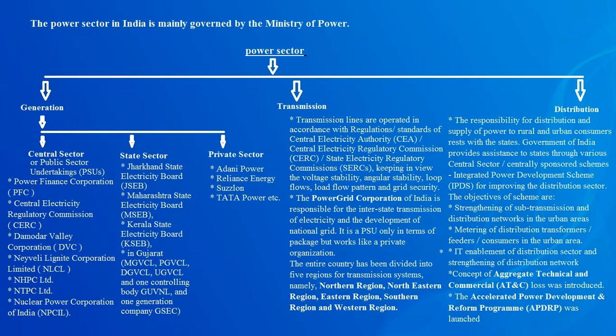The AT&C loss captures technical as well as commercial losses in the network and is a true indicator of total losses in the system. High technical losses in the system are primarily due to inadequate investments over the years for system improvement works, which has resulted in unplanned extensions of the distribution lines, overloading of the system elements like transformers and conductors, and lack of adequate reactive power support. The commercial losses are mainly due to low metering efficiency, theft and pilferages. This may be eliminated by improving metering efficiency, proper energy accounting and auditing, and improved billing and collection efficiency.